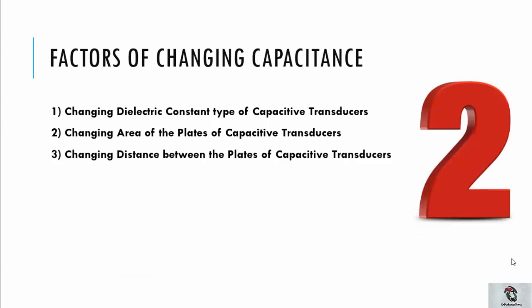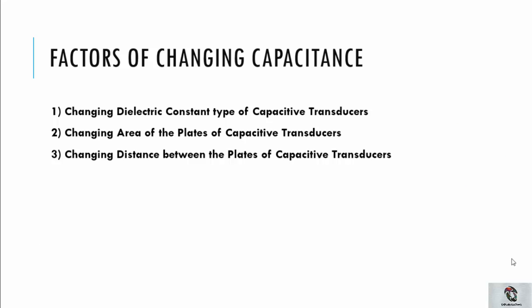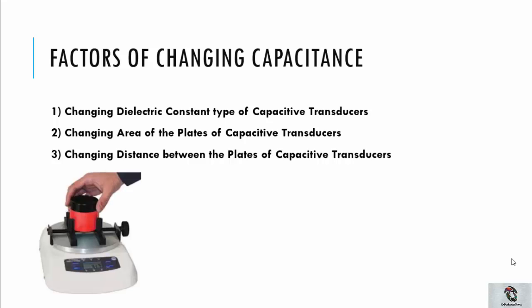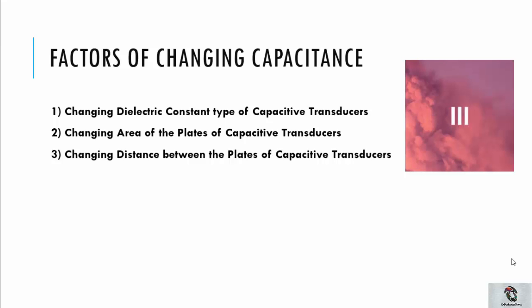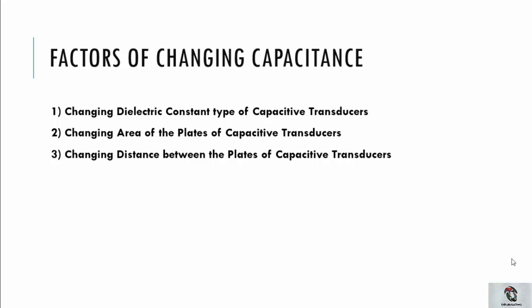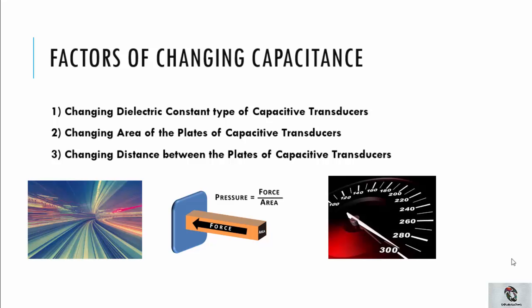The second factor is changing area of the plates. This is used in a torque meter for measurement of torque on a shaft, which comprises sleeves that have teeth cut axially and a matching shaft with similar teeth at its periphery. The third factor is changing distance between the plates. This concept is used for measurement of displacement of an object, where one plate of the transducer is kept fixed while the other is connected to the object. The change in capacitance is measured and calibrated against the input quantity, which is displacement. Quantities like velocity, pressure, and acceleration can also be measured through it.